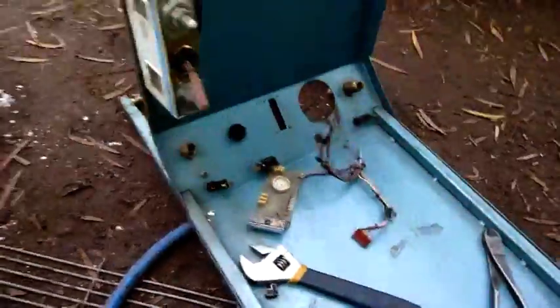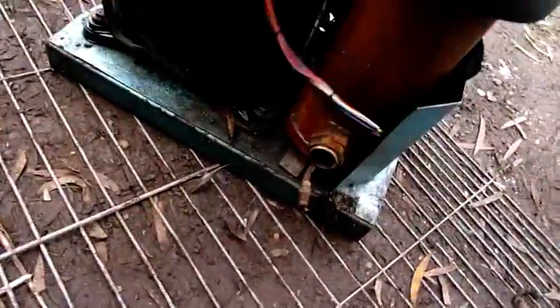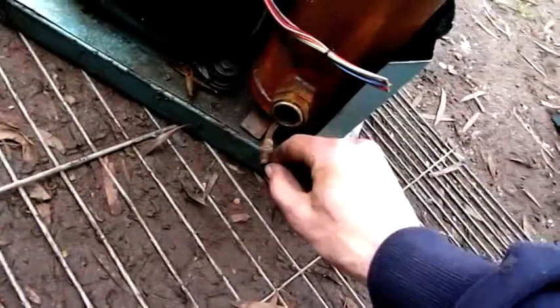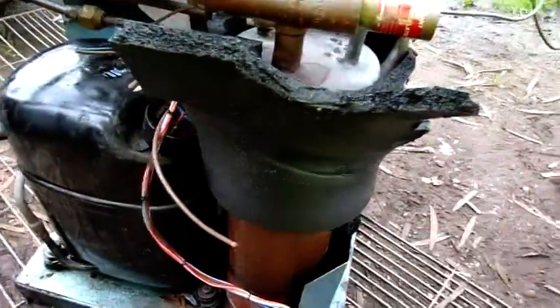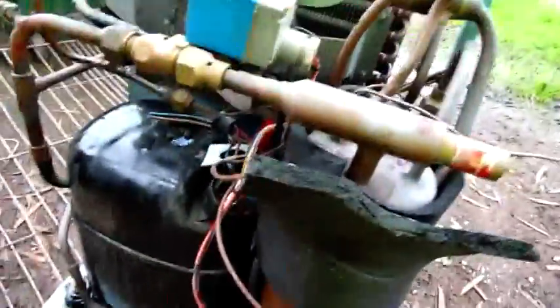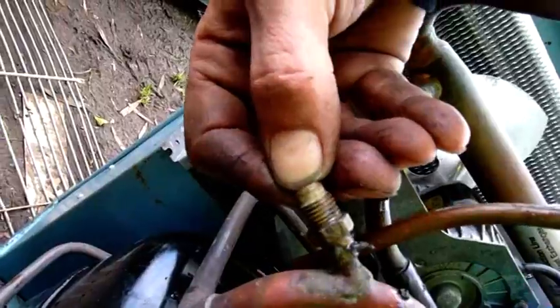Made in Philippines — cool. That is an oil accumulator or something; I guess that's an oil drain, nothing coming out but yeah. Still a little bit of gas pressure on the suction side, but that's because there are check valves and solenoid valves. So always check pressures on something like this because some sides will still hold pressure because of all the valves in it. But this one here is pretty much out, so it's just safe to strip down. No pressure left — that's good.